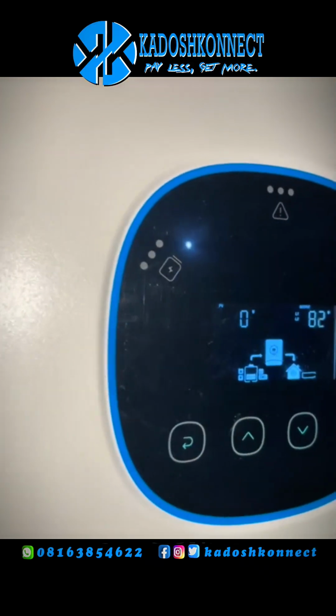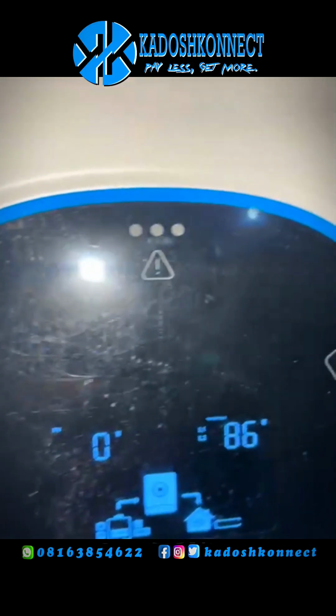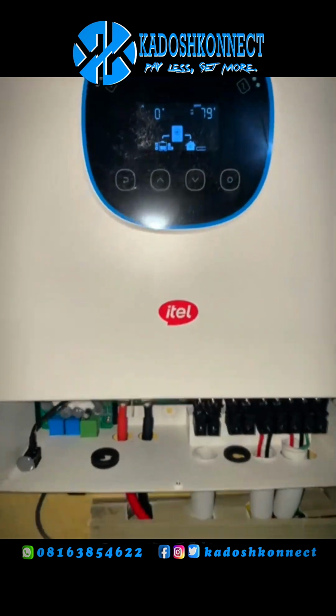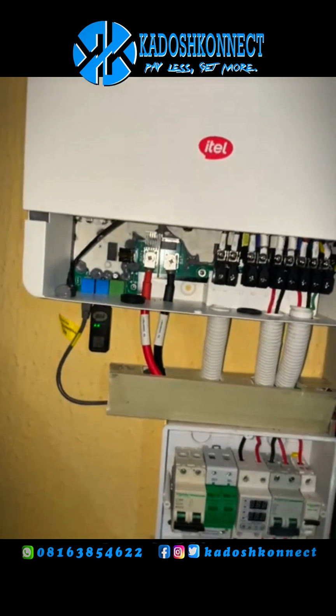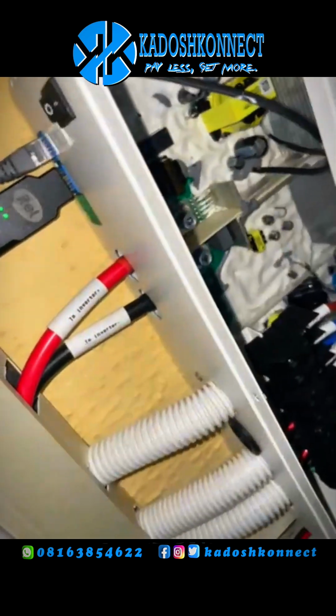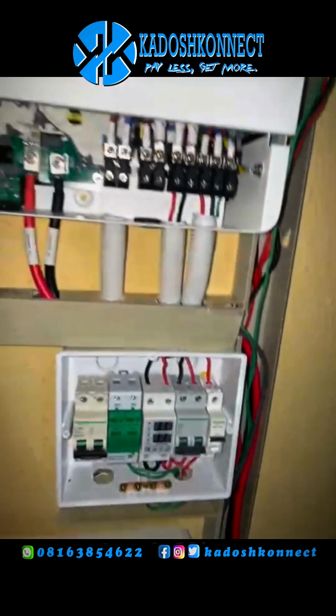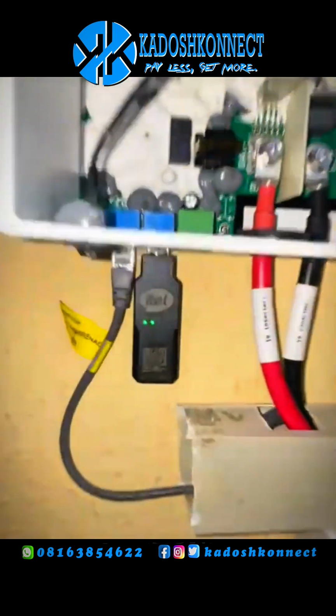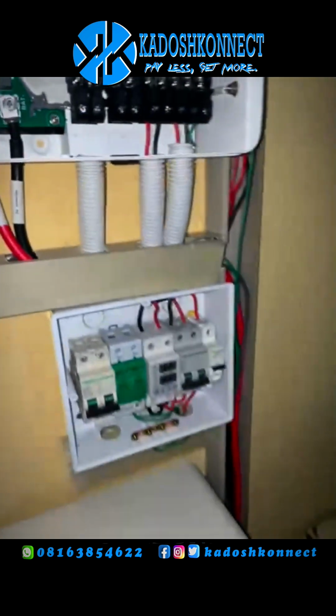So the reason why it was flagging an error at this point was because I've set it to lithium, but I've not actually done the communication, I've not changed the communication port. But at this point, the lithium was working fine, the BMS was communicating, so it started flagging that error.